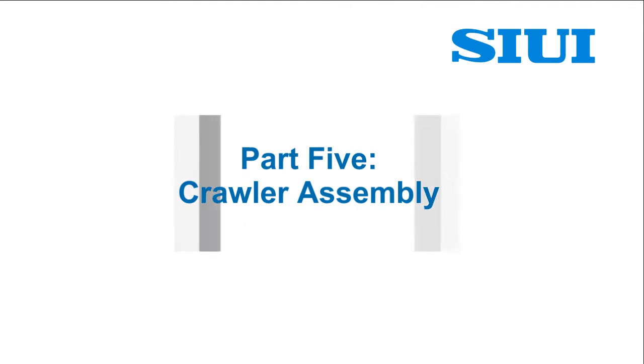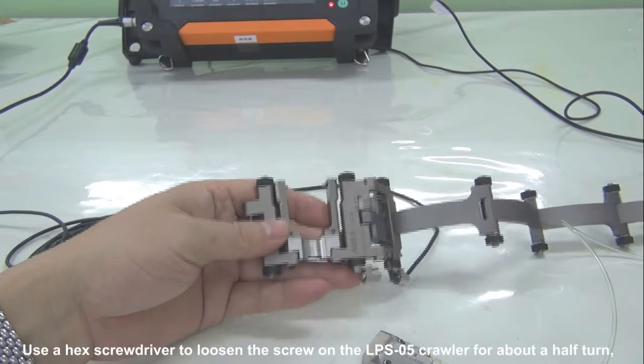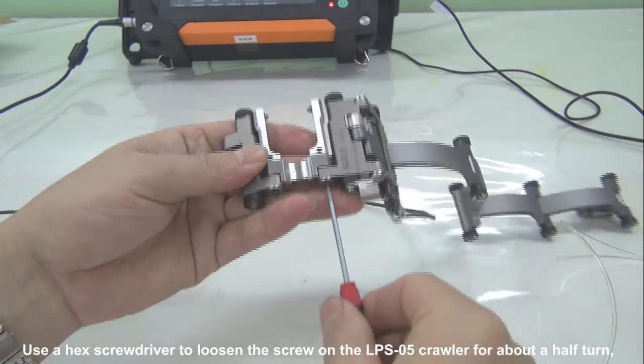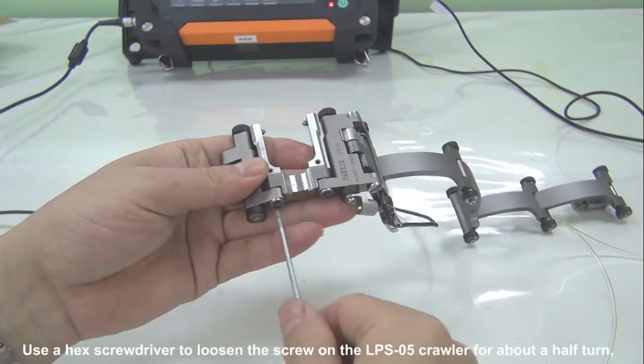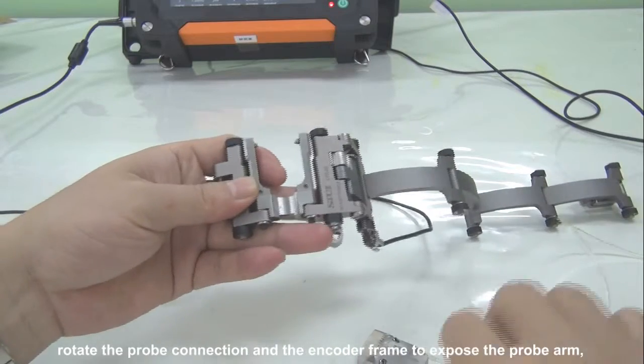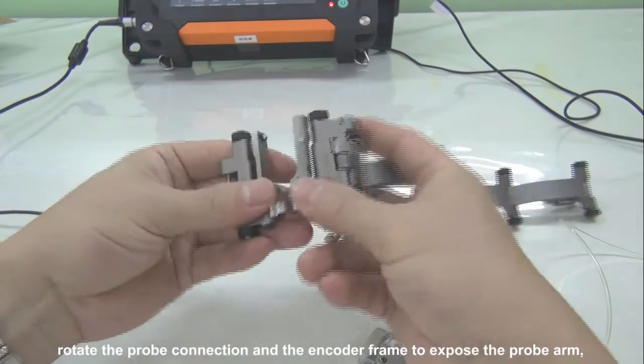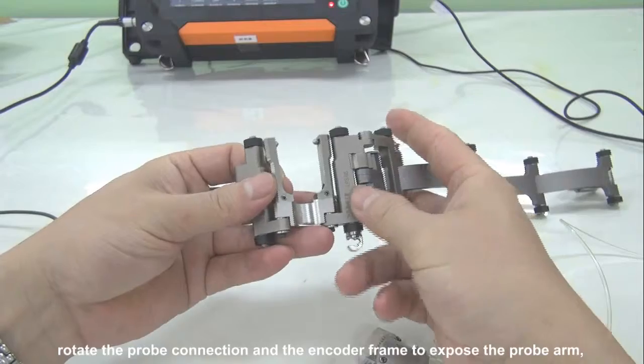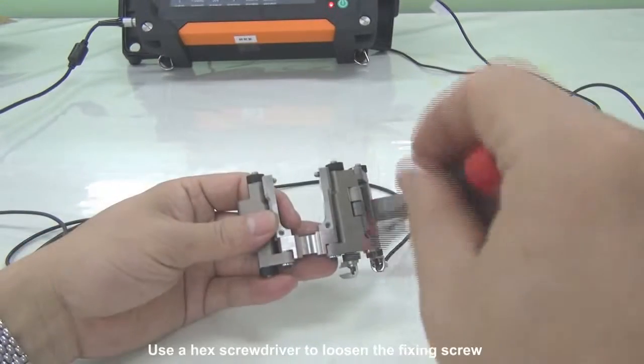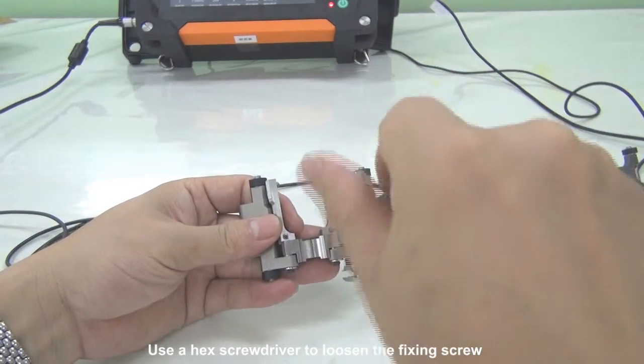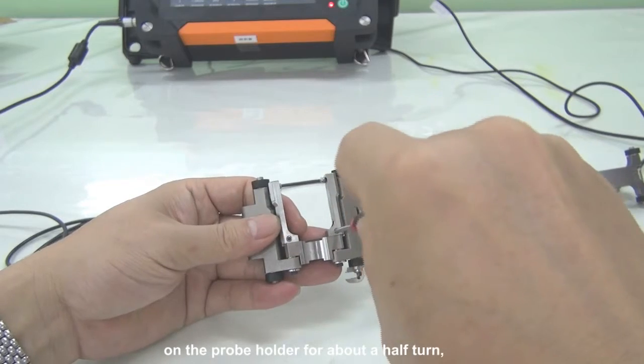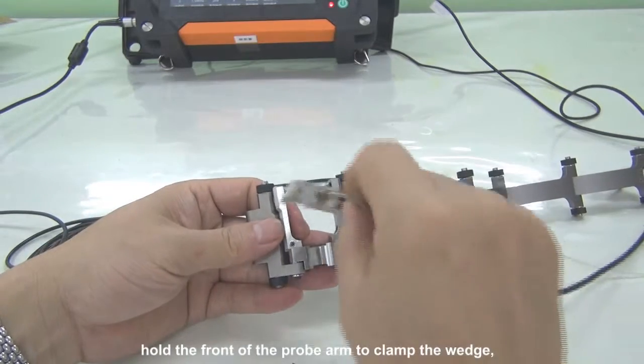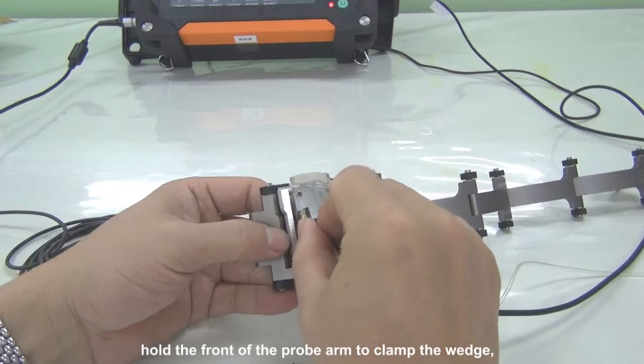Part 5. Crawler Assembly. Use the hex screwdriver to loosen the screw on the LPS 05 crawler for about half a turn. Rotate the probe connection and the encoder frame to expose the probe arm, so that it may travel outward. Use the hex screwdriver to loosen the fixing screw on the probe holder for about half a turn. Hold the front of the probe arm to clamp the wedge.